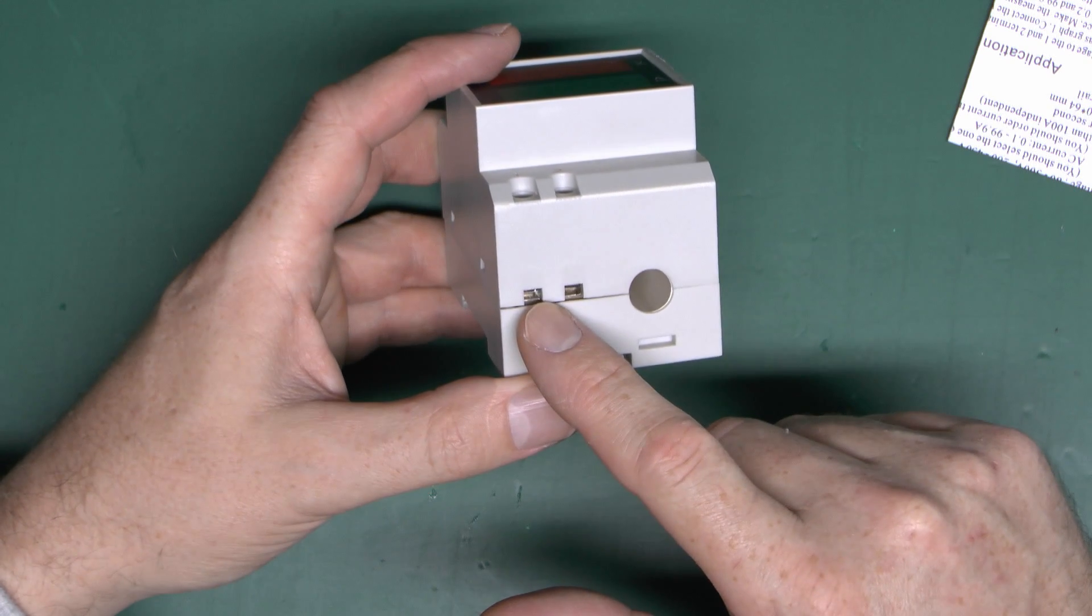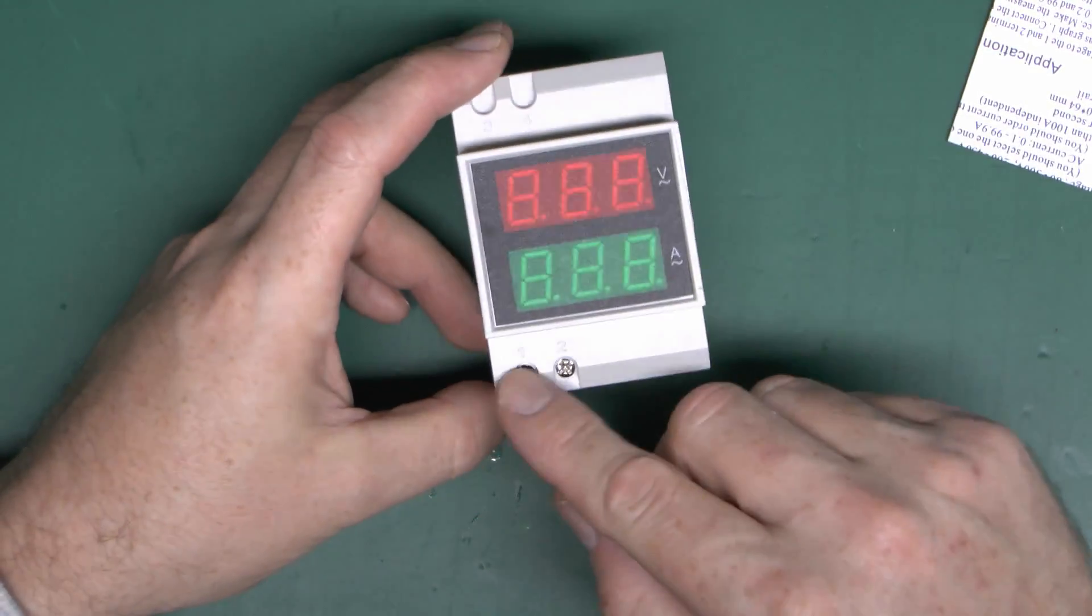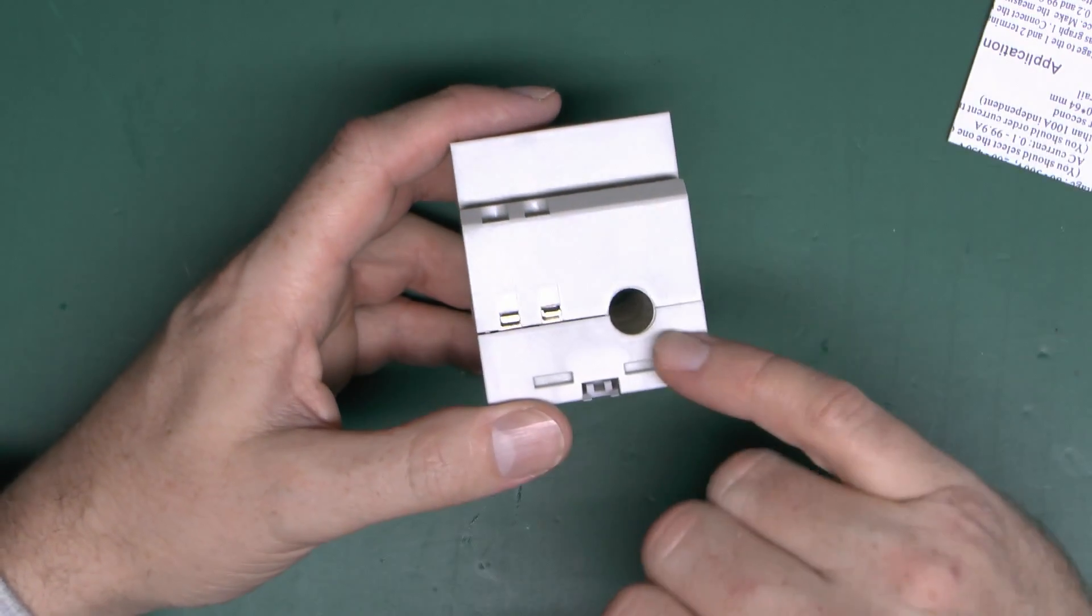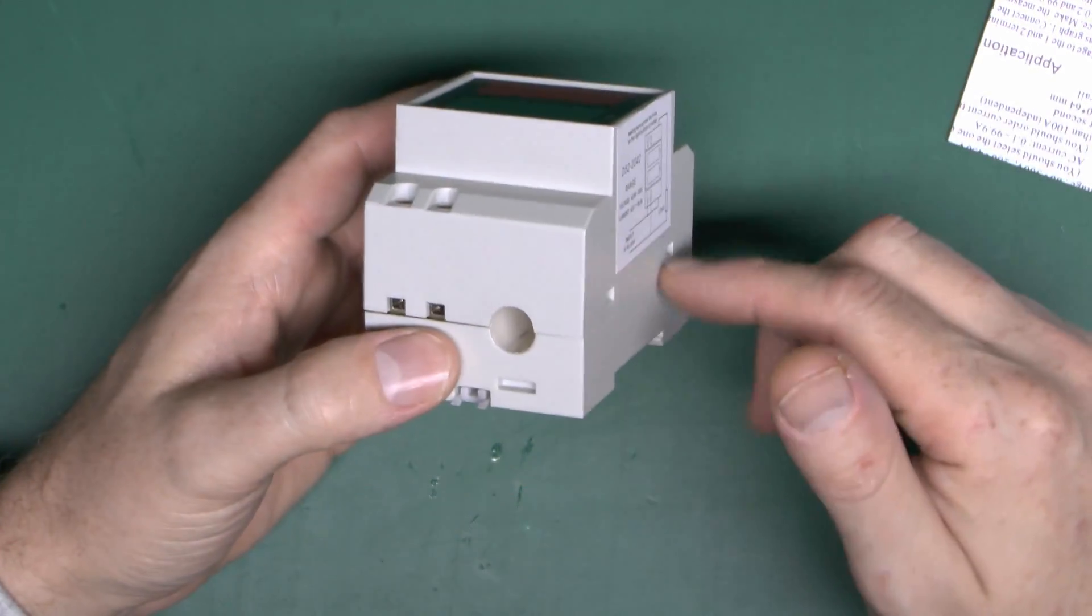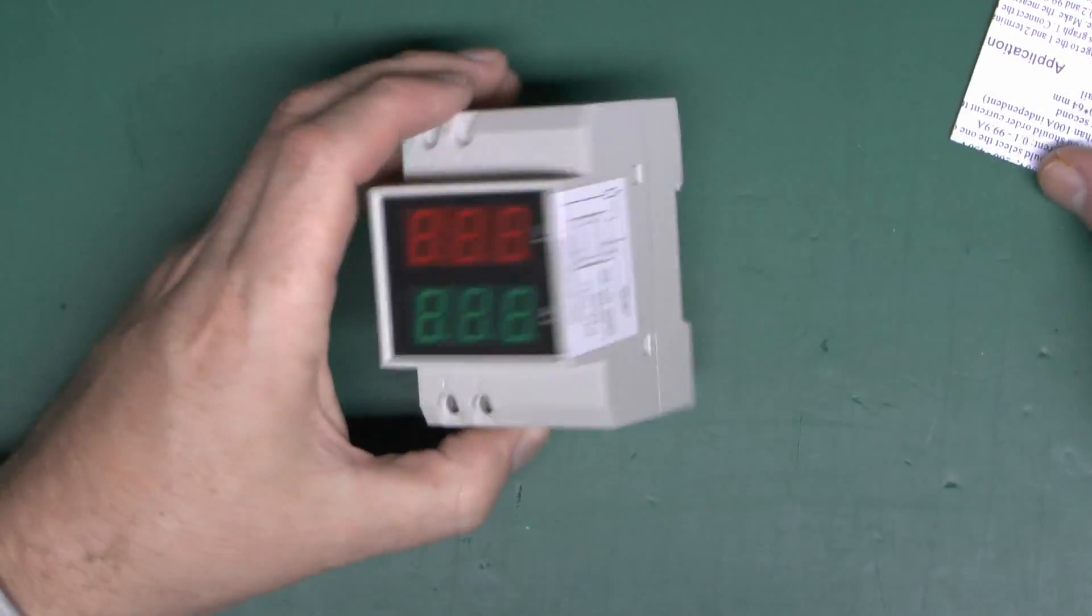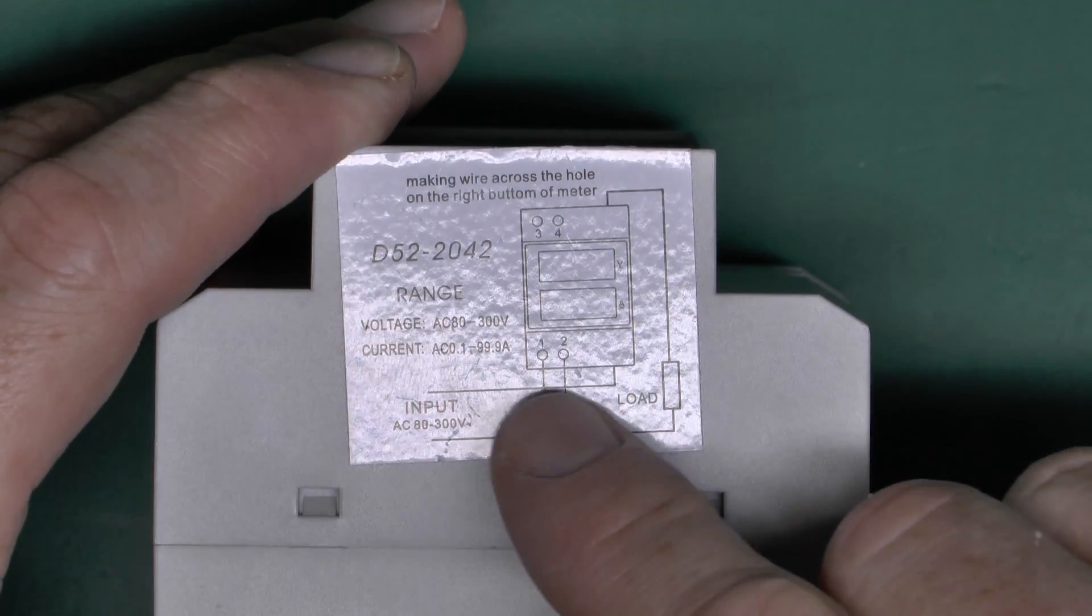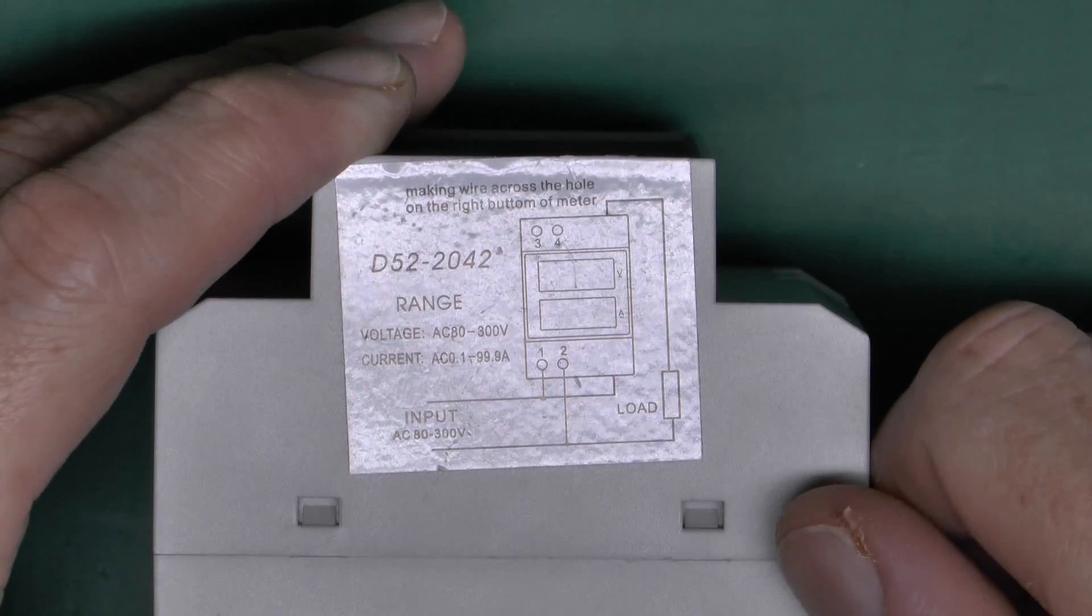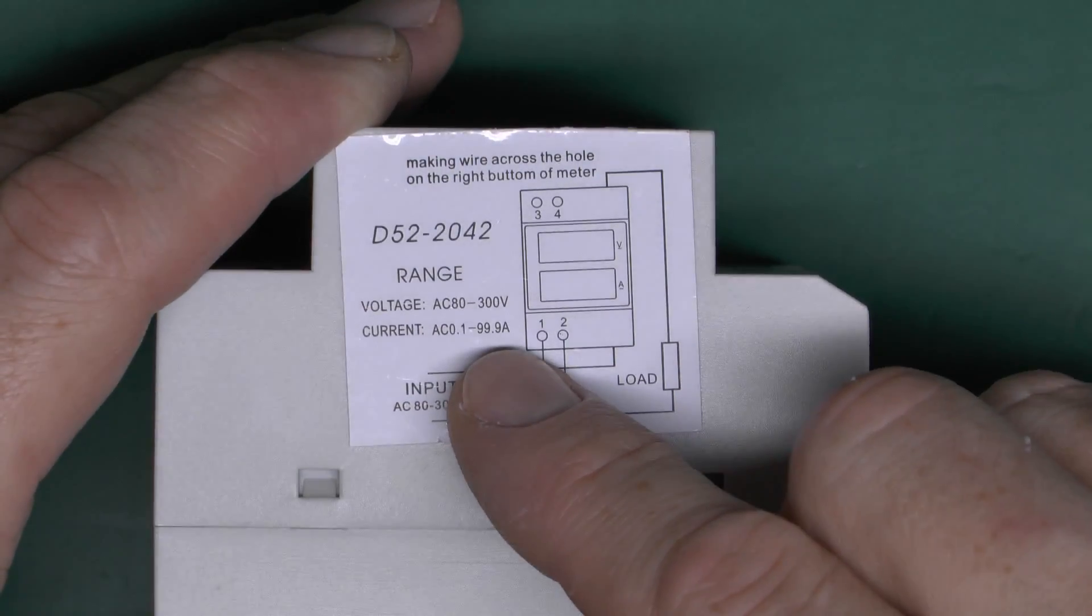The way these things work, they only have two connections. The two wires go in the bottom here, and that's basically your main supply - 240 volts or whatever voltage you're using, just the two terminals. That powers the device and is where it's measuring the voltage from as well. For the current, it's actually done through this hole. You're essentially just passing the wire through the hole there, and there's a current transformer inside which measures the current and displays it on the green display on the front. Voltage on this is 80 to 300, and current is 0.1 to 99.9 amps. Quite a wide range there.